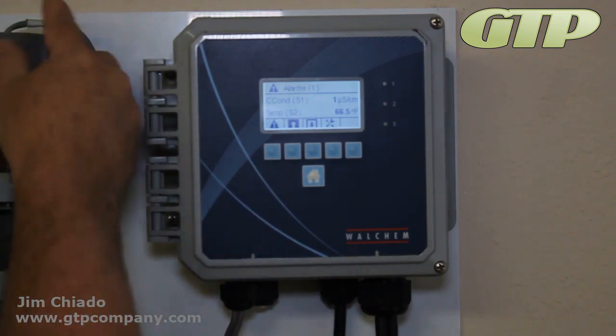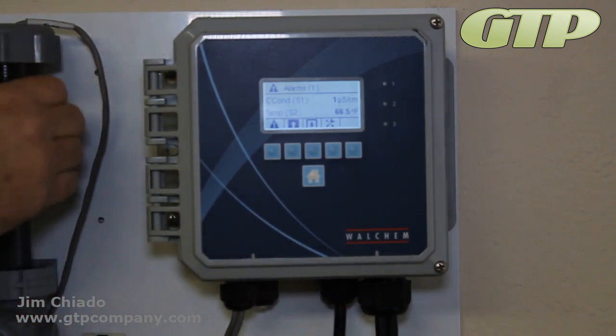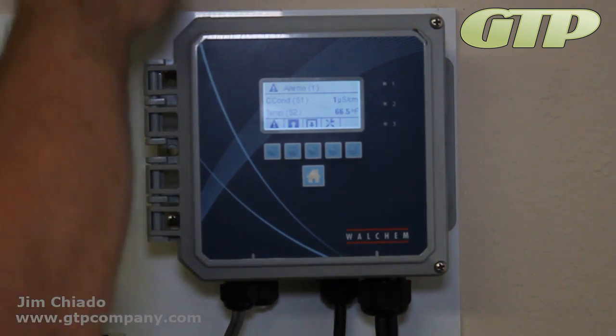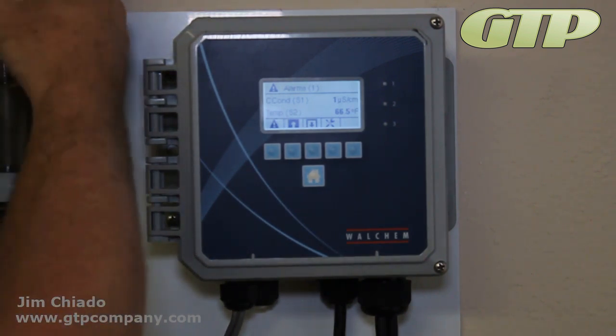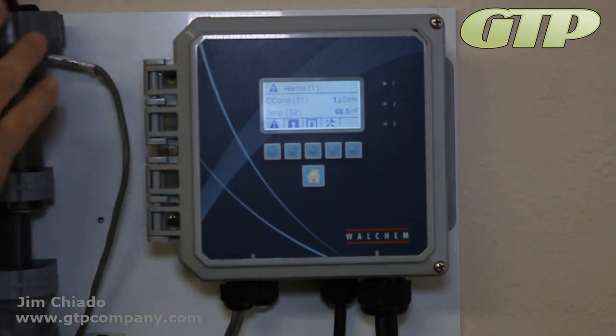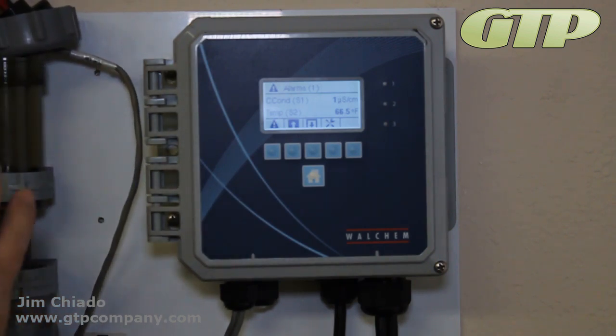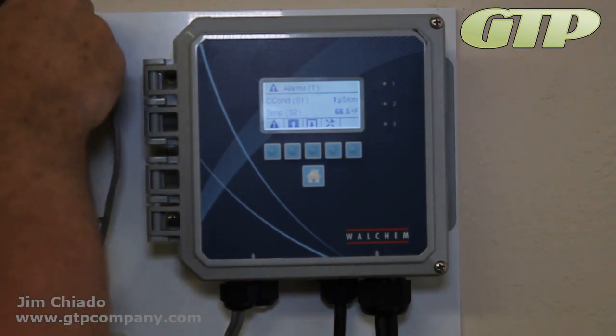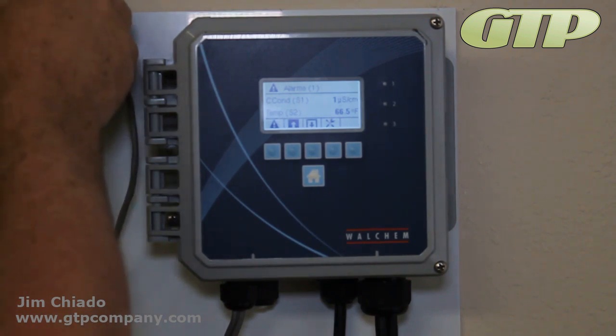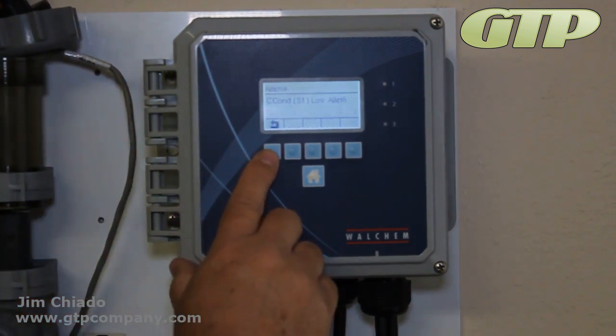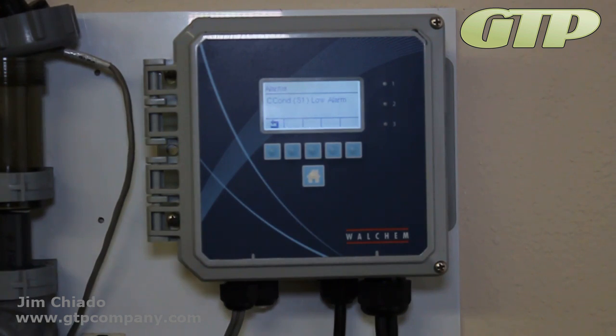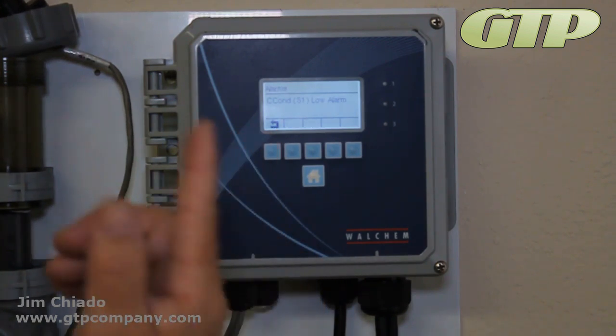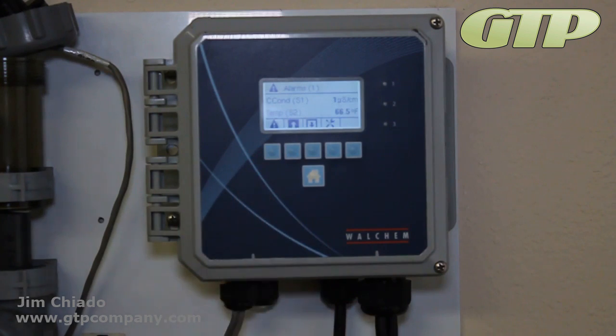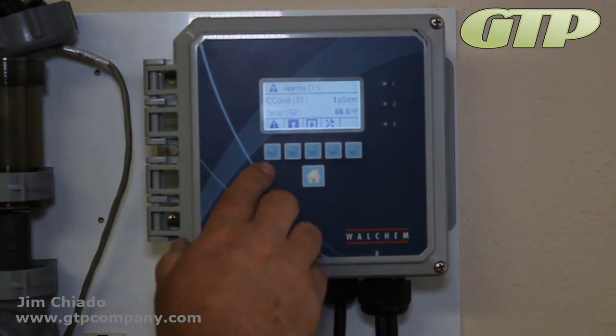Right now the alarm is on the flow. The only way to fix that is to change the condition of the flow, turn it on, or if I come over here and turn the flow switch upside down, it's going to take it off. Now it's on conductivity. So the conductivity is low. It didn't disappear and I wondered why. You don't really just switch from flow switch to conductivity. Since there is flow, it'll let you alarm on conductivity.